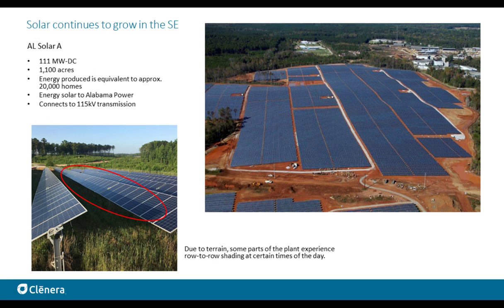but you're not able to know if one row should be adjusted independent of its neighbor. So we've now enabled TRUECAPTURE on the majority of the site, but in particular, there are a few power blocks where we turned TRUECAPTURE backtracking on for one day and off for the next, and alternated back and forth. That really provides us with an opportunity to compare what the real benefit is, outside of just geometry and doing the physics ourselves on a piece of paper.